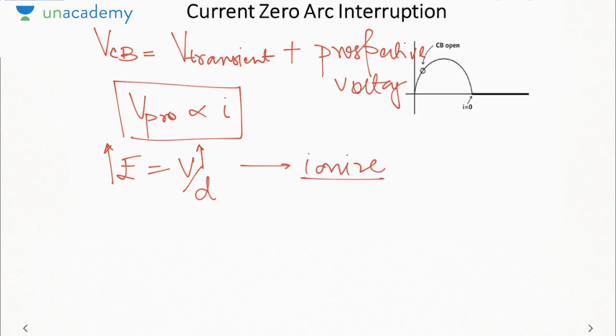So that means even if you are extinguishing the arc, due to this high voltage produced, more charge carriers will be generated and the arc will continue to exist. It is called restriking — the arc will restrike because there is a high voltage across the circuit breaker.